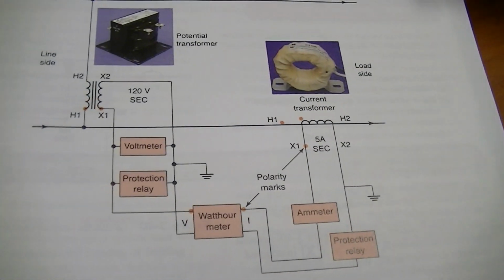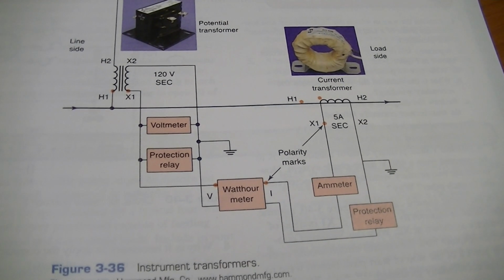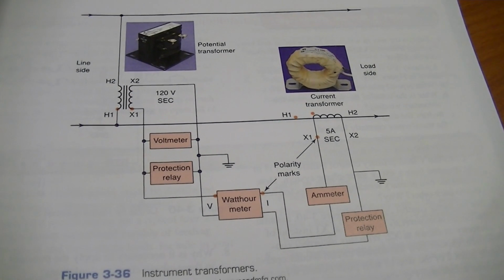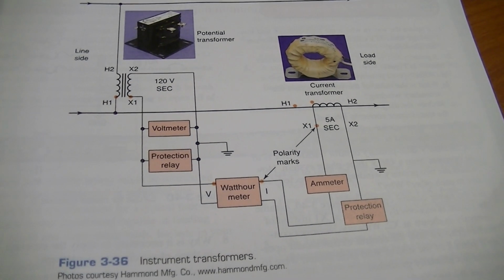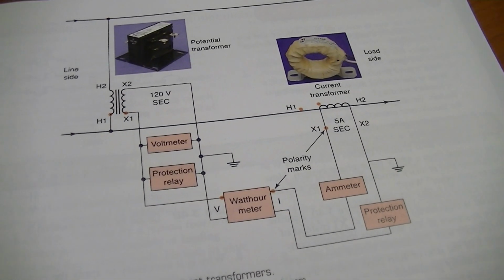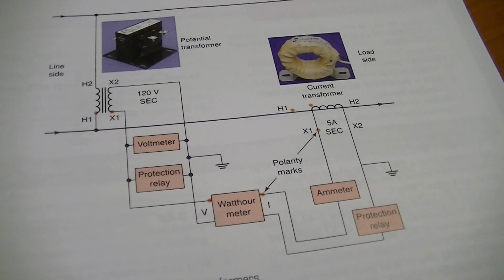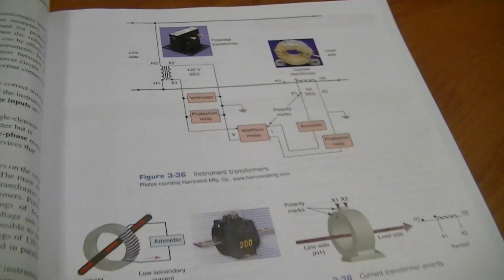I've seen many different types of current transformers. Okay, this would be a potential transformer. What's a potential transformer? It's a transformer. It's got step up, step down. Typically it's step down. If you've got a 44,000 volt system and you want to get it down to 110 volts, you need to step it down via a transformer. Why do you want it to get down to 120 volts? Because that's what I'm using in the instrument that's protecting, for example. It's using that ratio and looking at the actual current, using that multiplier and figuring out what the line voltage is, what the line current is, and then using the multiplication factor in there. It'll trip at a certain set point.